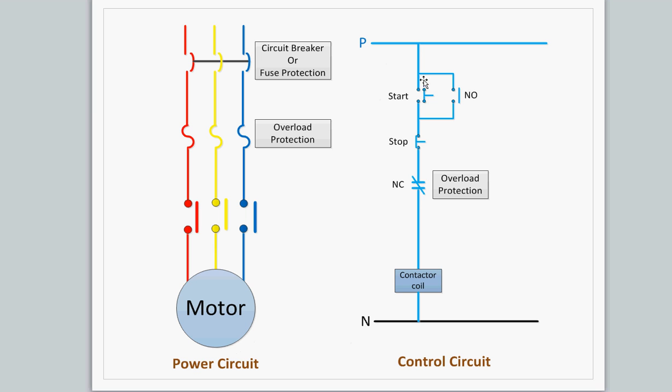In the control circuit, you can see here when the operator presses the start button, the circuit closes and the contactor activates. At that time, it closes all these three contacts. Once the operator removes the start button, the current continuously flows through this normally open contact of the contactor. Once it's activated, this contact gets closed and now the circuit will flow from this side here.